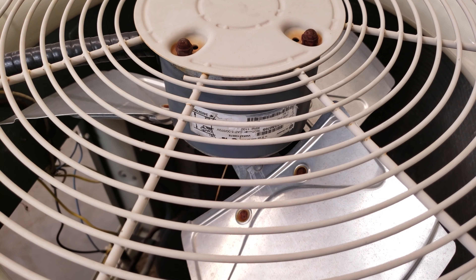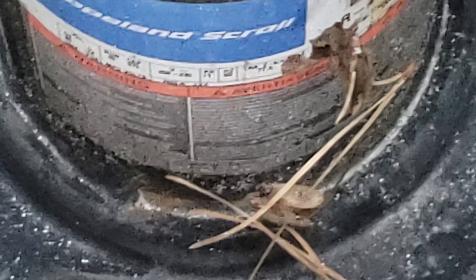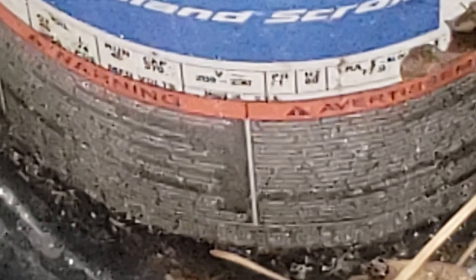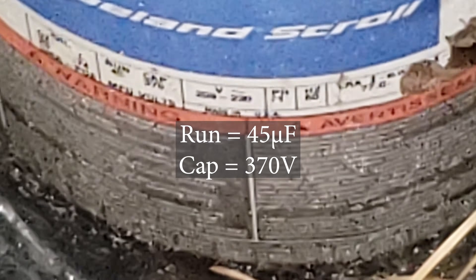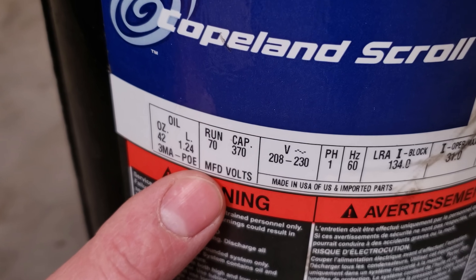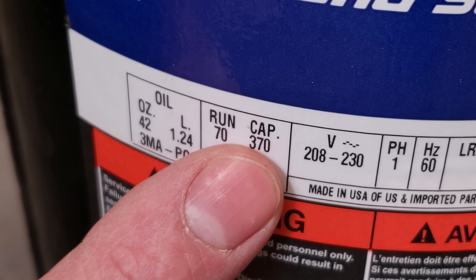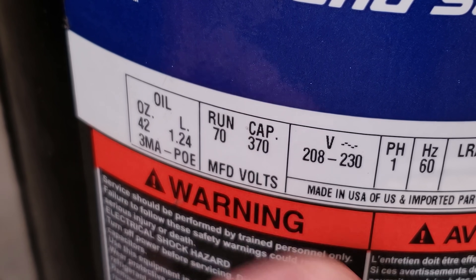Zoom into the rating plate with your phone — a lot of times there's no ready-access door on the side of the unit. On this compressor plate, below 'RUN' it says 70, and under 'CAP' it says 370 — meaning it needs a 70 UF, 370-volt capacitor. On a different compressor, the MFD needed is 70 and the voltage must be 370 or higher.